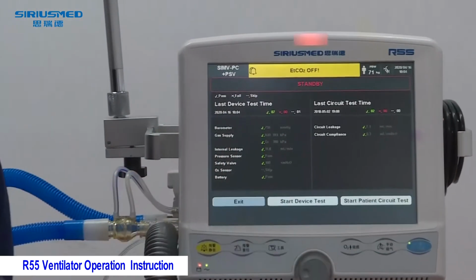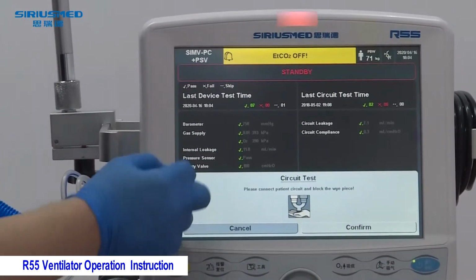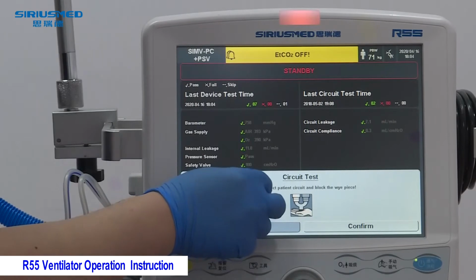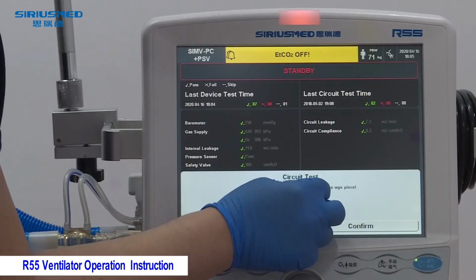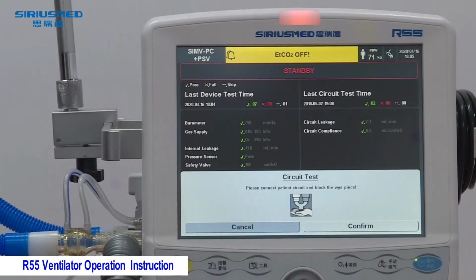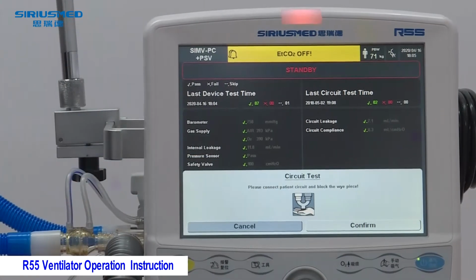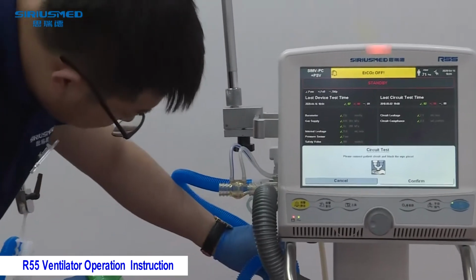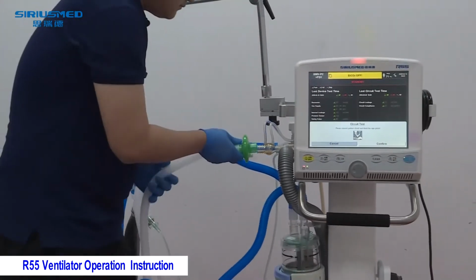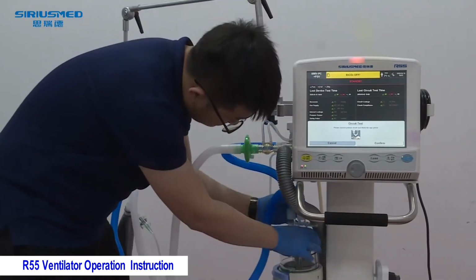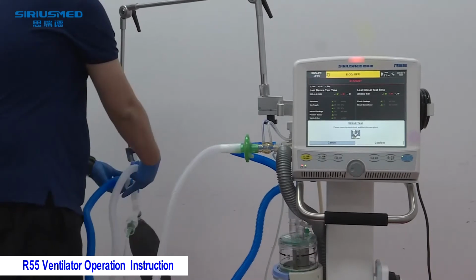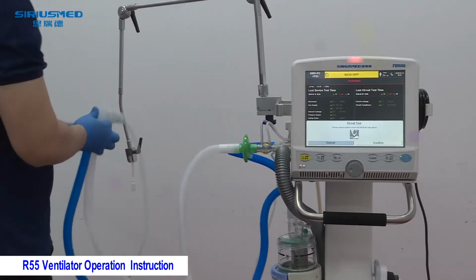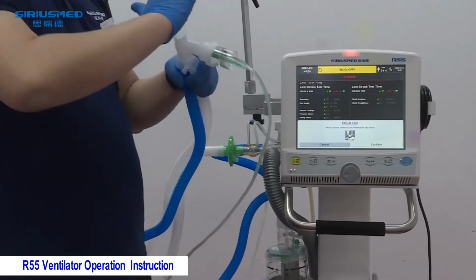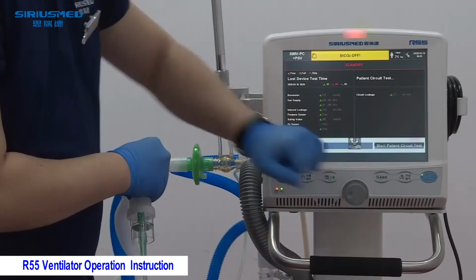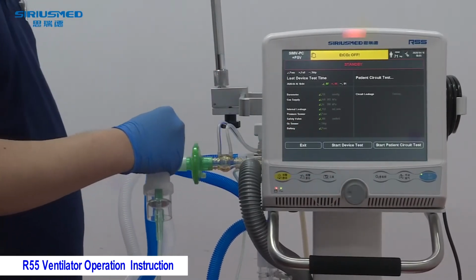About the circuit test, also we need to confirm firstly and then read the instruction. It means please connect the patient circuit and block the wye piece. It means you need to connect the tube as in normal use and then use your hand to hold the wye piece. Use your hand to hold the wye piece and then press confirm. Also, it will be done automatically.